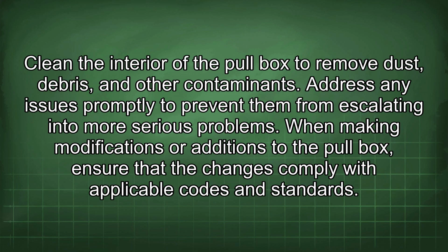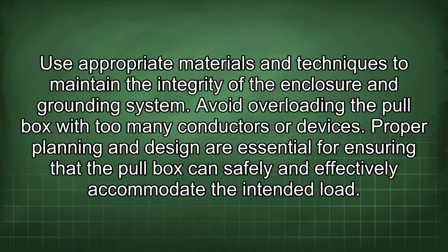Clean the interior of the pull box to remove dust, debris, and other contaminants. Address any issues promptly to prevent them from escalating into more serious problems. When making modifications or additions to the pull box, ensure that the changes comply with applicable codes and standards. Use appropriate materials and techniques to maintain the integrity of the enclosure and grounding system. Avoid overloading the pull box with too many conductors or devices. Proper planning and design are essential for ensuring that the pull box can safely and effectively accommodate the intended load.